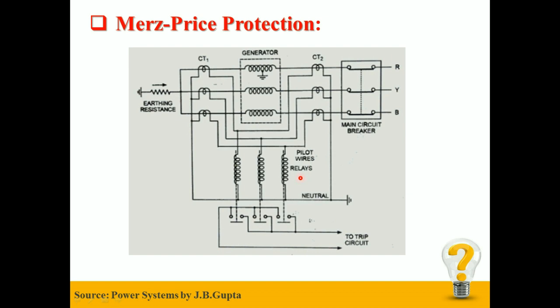But under abnormal condition, currents at both ends will no longer be similar. Therefore, the induced EMF in the CT secondaries will not be equal. This will lead to a differential current flowing through the relay operating coil, which will send a trip signal in order to protect the stator winding of the three-phase generator.